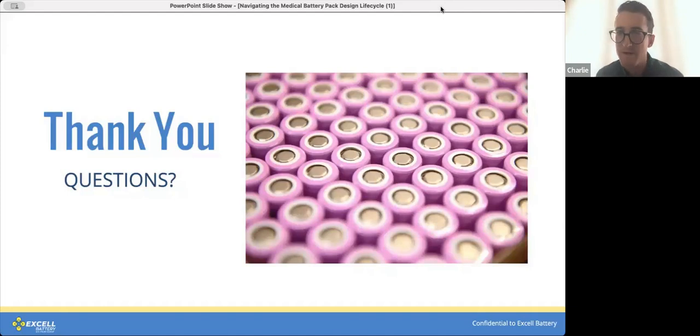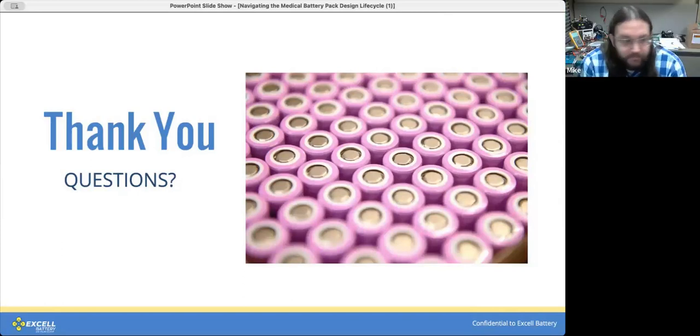Just bear with me for a moment. I'll send it off to one of our panelists who I feel is best to answer this question. Let's start out maybe with Mike on this one. What does UL 2054 do on top of IEC 62133? The tests are fairly similar, but UL 2054 on top of IEC 62133 also adds faulted testing. For those tests they'll bypass certain protective components on the board within the battery, fuses, FETs, whatever, to simulate some of the common failure modes and test it with those faults in place, and it's still got to be safe.